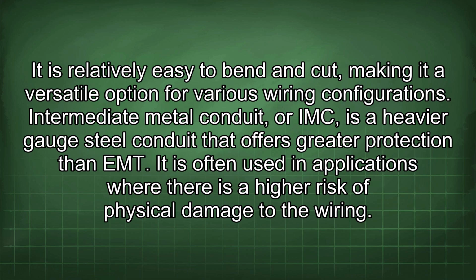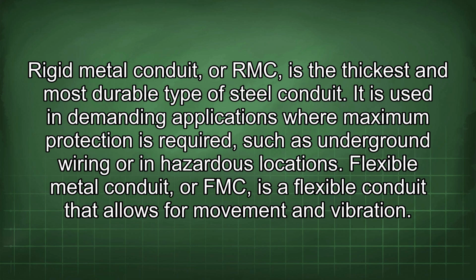It is often used in applications where there is a higher risk of physical damage to the wiring. Rigid metal conduit, or RMC, is the thickest and most durable type of steel conduit. It is used in demanding applications where maximum protection is required, such as underground wiring or in hazardous locations.